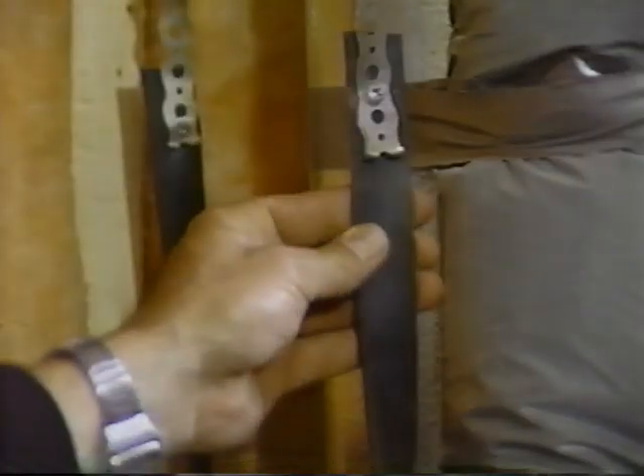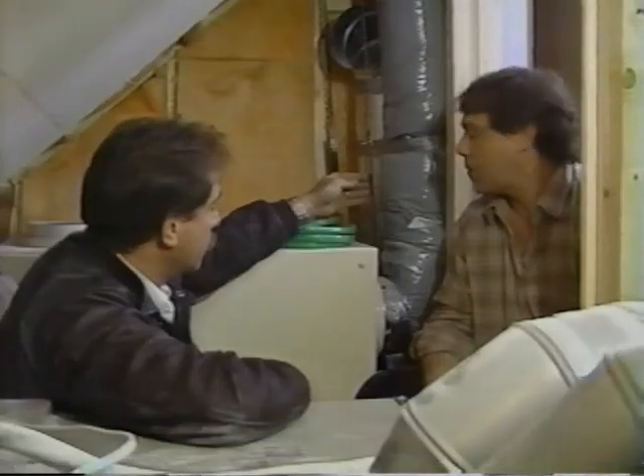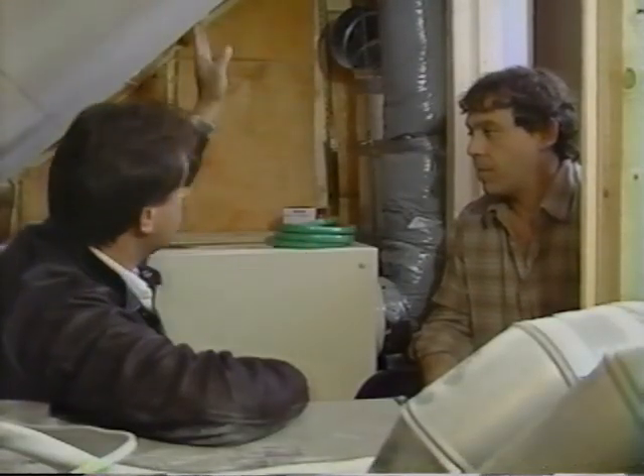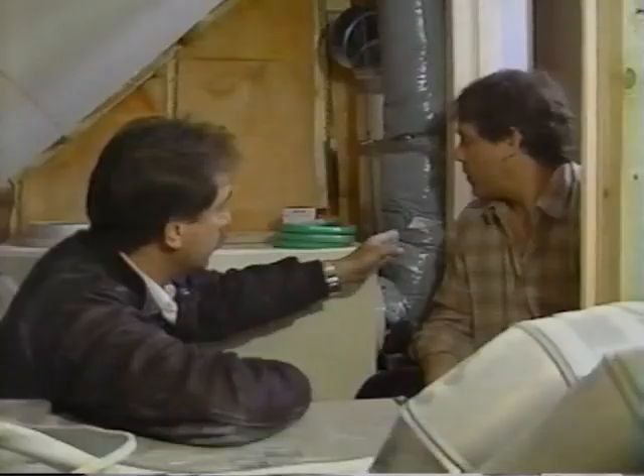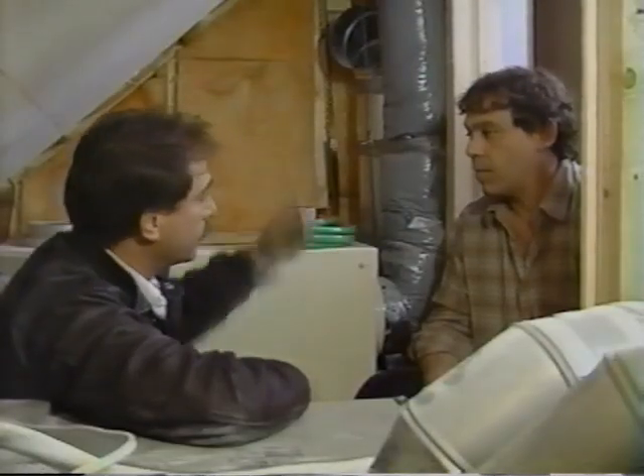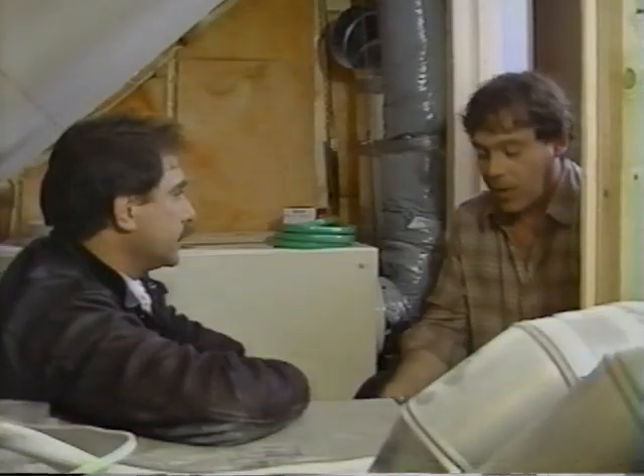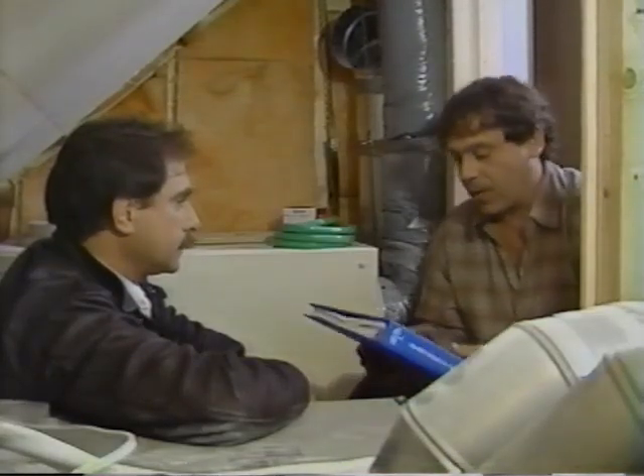Yeah, they're fairly common. The point here is that you've got to have rubber straps in order to isolate this unit for vibration against the frame, and you also want to insulate the ductwork to cut down any of the vibration that's in the duct itself. Right. How did you learn all this stuff? Oh, well, while you were gone, I was busy being nosy, thumbing through the installer's manual for heat recovery ventilators.